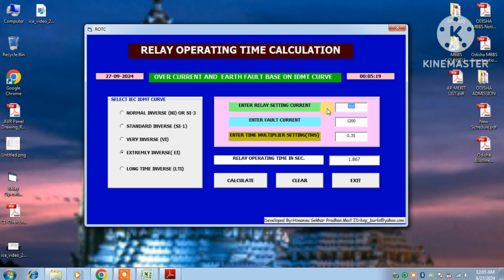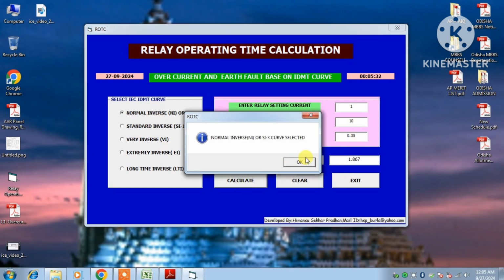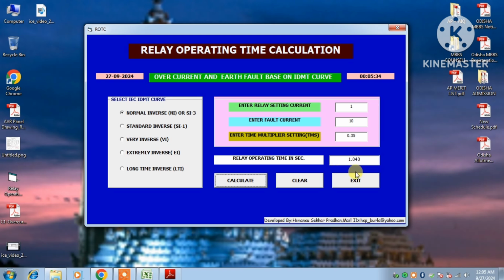Suppose we take the secondary value, where full load current is 300/1, then 1 amp. If you take 10 times the fault current, you can enter 10. In the same way, if you select the normal inverse curve and calculate, it automatically calculates that it will operate in 1.040 seconds. We'll take one example. First we'll click clear, and it will clear.